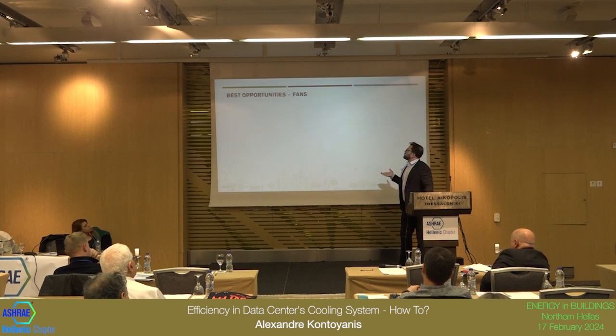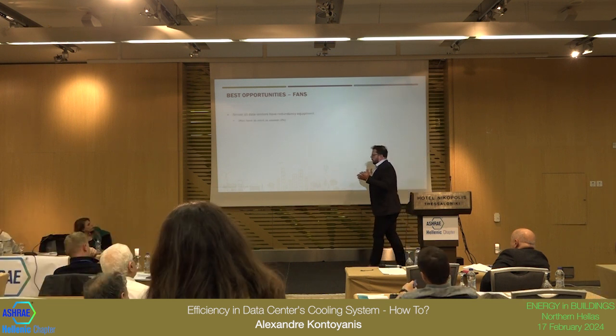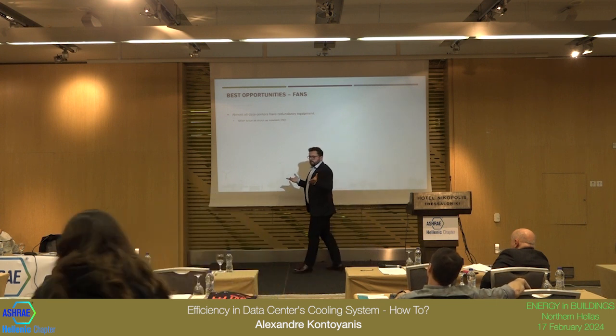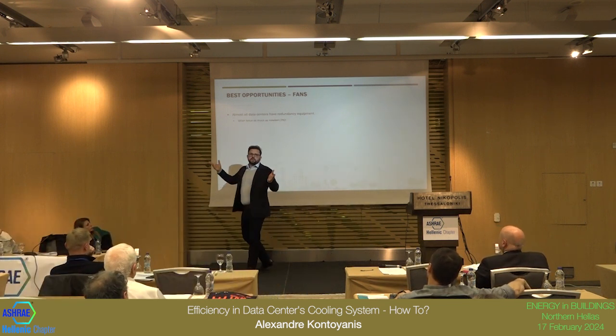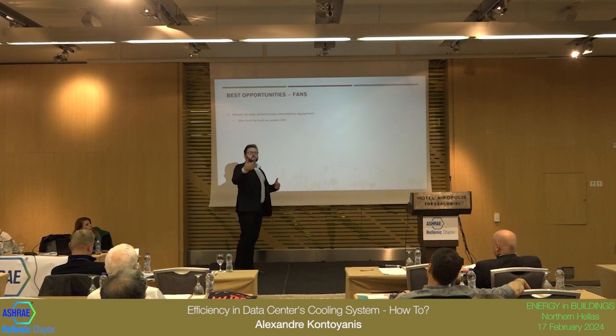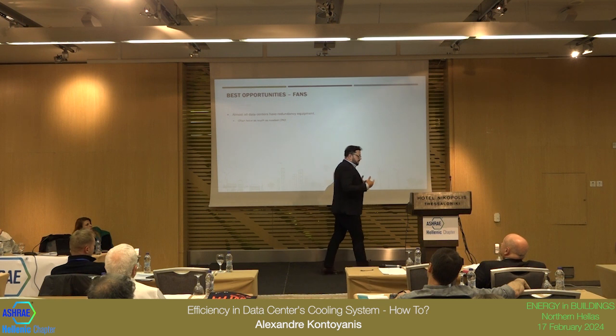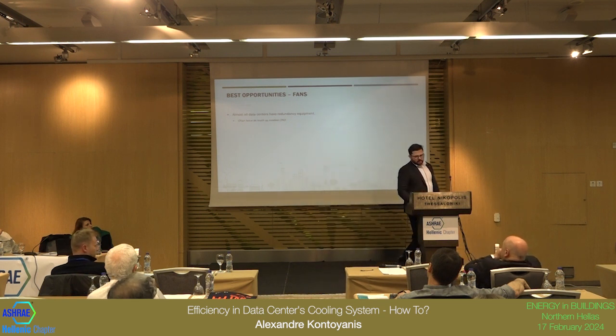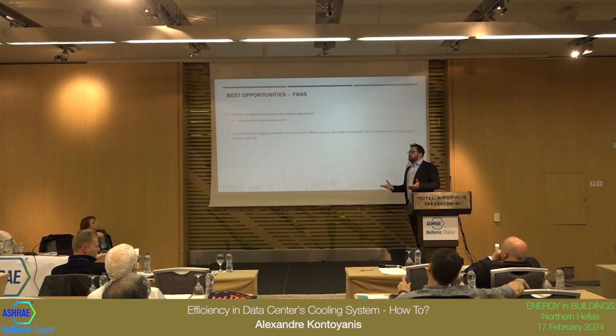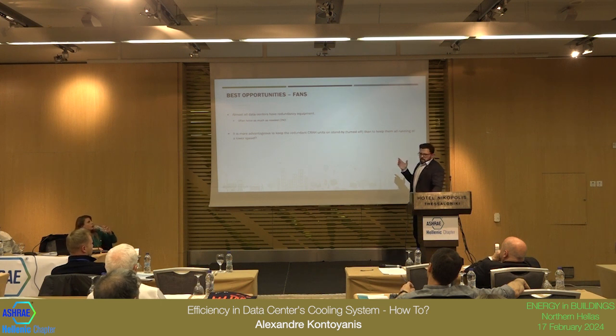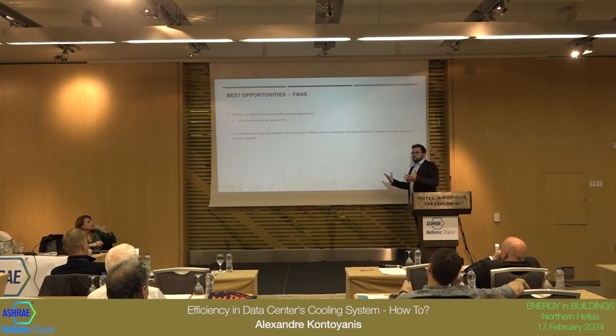And the second last one that I want to talk to you about is fans. We know almost every data center has redundancy, often twice as much as needed. We call it 2N. I have 2N data centers, N plus 1 data centers. If you have double the capacity that you need, it's just fine because you need 100% uptime. The question is, is it more advantageous to keep redundant fan units on standby, meaning turned off, than to keep them all running together at a lower speed?